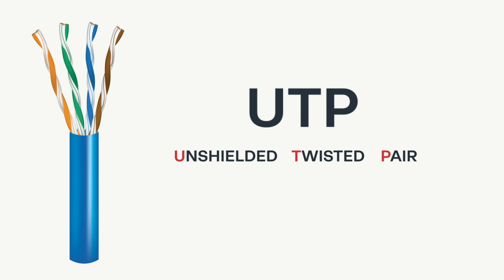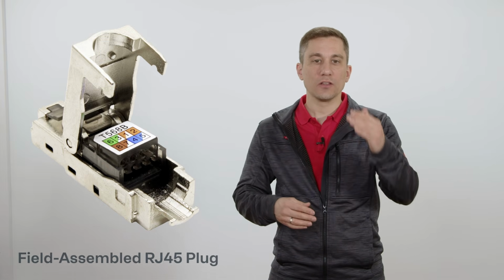However, there are also so-called UTP cables on the market, unshielded twisted pair cables, and we do not recommend you to use them since there is no shield at all, meaning that all different kinds of signals can couple onto these lines, leading to data communication errors in the operation. For the actual plug, we always recommend you to use field connectors.